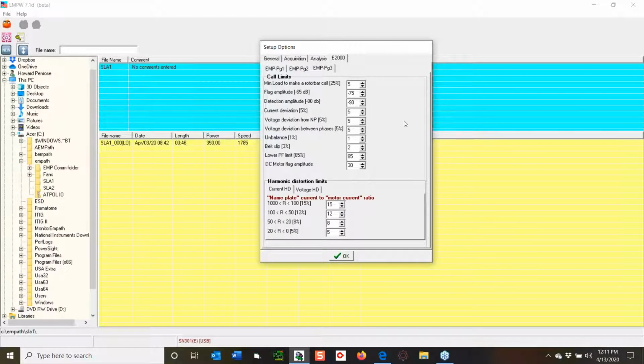This big one I asked the programmer to do, and he thankfully did. It allows me to set all of my minimums. Because of the resolution of the EMPATH system, you'll see here it says minimum load to make a rotor bar call — I set it at 5%. The default is 25%. 5% means it's not loaded. So if I go into a repair shop and the motor's sitting there running on the floor, across the line, full voltage, the resolution of this system will still distinguish the peaks.